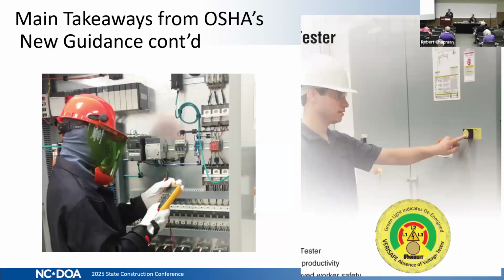So how do you do that? What you see here on the slide are 2 pictures. One on the left is a maintenance person who's getting ready to take measurements to prove that the equipment is de-energized before they start performing their maintenance tasks. The picture on the right is the same piece of equipment, but in this case, it has on the door something called an AVT, or absence of voltage tester.